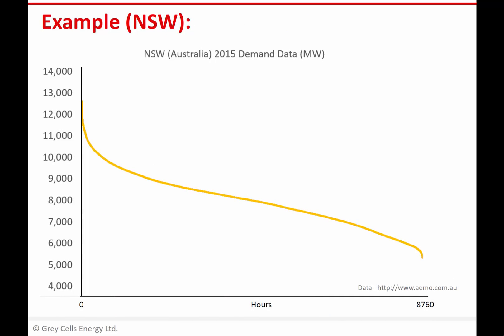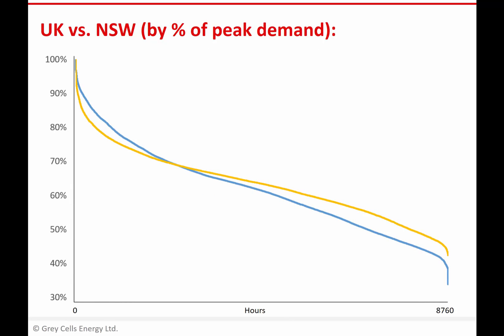Here's the load duration curve for 2015 for the New South Wales region of Australia — a very similar shape with a very steep uptick towards the peak values. So those peak values above 11,000 megawatts occurred for very few hours during the year. Given the different scales of the UK versus New South Wales, an easier way to compare the two load duration curves is to plot them not in absolute values but in terms of percentage of peak demand. The two curves converge at 100% of peak demand, but the New South Wales curve is much steeper than the UK one for those few hours towards the left where we have peak demand values.